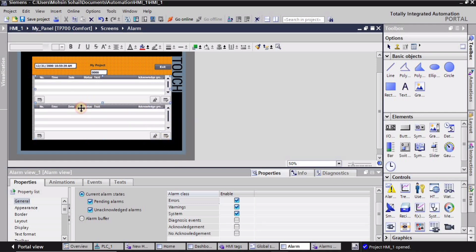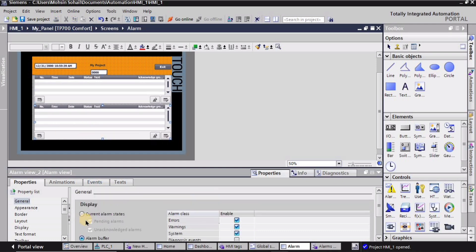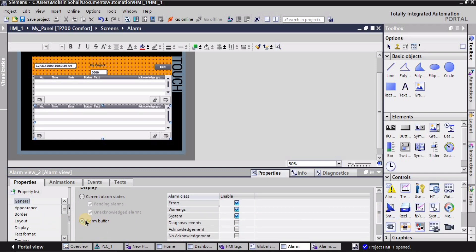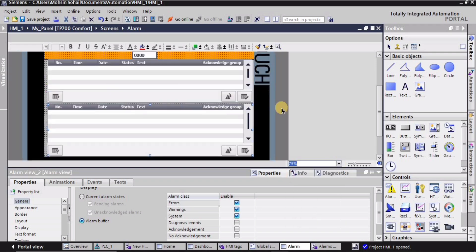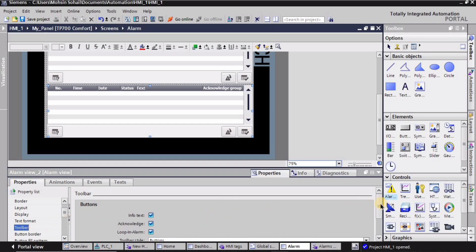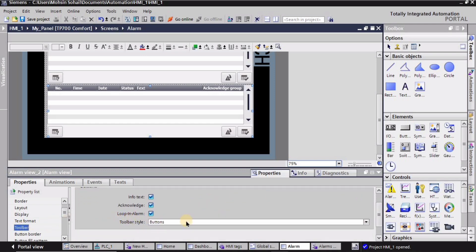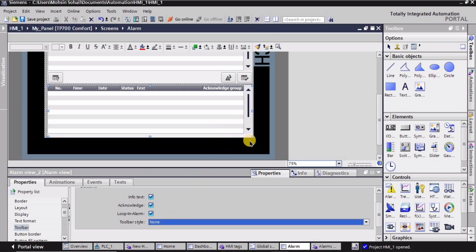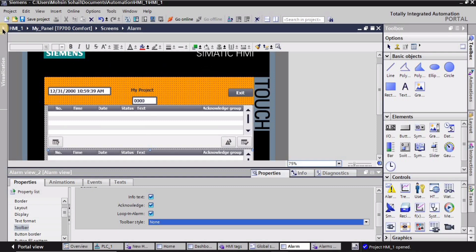For this screen, since I want the history for the alarms and warnings, I will be selecting the alarm buffer. Alarm buffer basically shows the history of alarms and warnings and the system messages — we will see it in the simulation part. Since I do not need these buttons in the second alarm view, I will select the toolbar. In the toolbar style I will select 'none' and as you can see the buttons are gone.